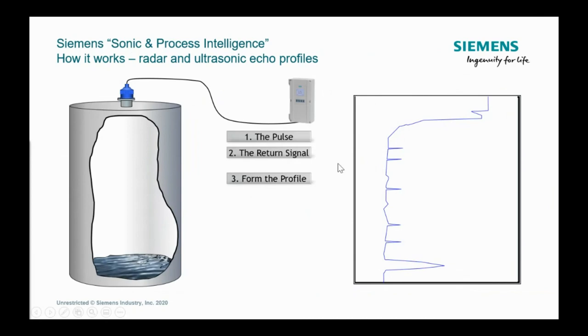Okay, so after it forms the echo profile, step number four is it's going to apply some filtering. There's a narrow echo and a spike filter that we're going to talk about in a couple slides. Then it's going to apply something called the TVT, a time-varying threshold. That red line is basically helping to filter out some of the noise, as you'll see down here at the noise floor. But the key takeaway is anything that is to the right or above this TVT line could be considered a valid echo. If we were in a live class, I'd ask the class, how many valid echoes do we have in this case? The answer should be one, because we only have one thing sticking up above it.